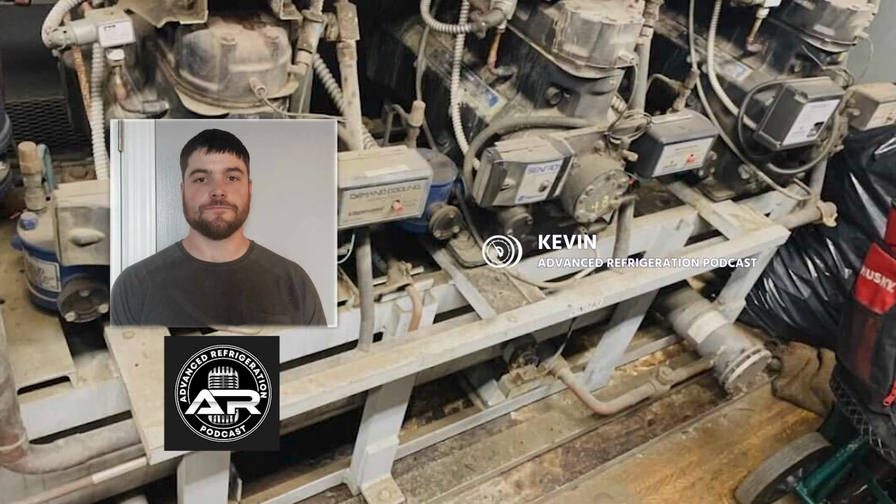Yeah, any places that have high humidity. When I was up in Connecticut, reheat just had to be there because otherwise the store would get super cold, but be miserably humid, because it would reach maybe 66 degrees in there since it would pull down so quick. Yet it needed that reheat to stay running, to keep the store a little bit warm, to keep a load on the compressor so they didn't actually maintain temperature. Yeah, it's actually fairly rare in Chicago now. They make it very difficult for us to have reheat with all their safety stuff.